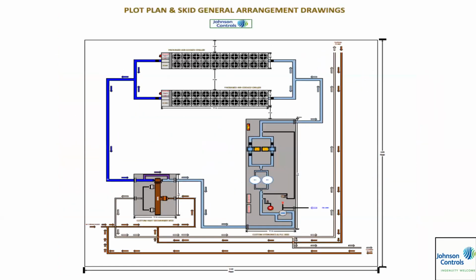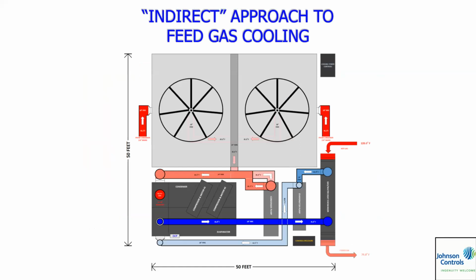This is pentane gas, 2 air cooled chillers with a pentane gas heat exchanger. Skid here, and then here was a pumping skid with buffer tanks and expansion modules. And again, I can show you a bunch of other examples, but this is one with cooling towers. The two cell cooling tower, big double compressor chiller. And in this case, they had no redundancy, which was crazy. So they only wanted 1 condenser pump, 1 evaporator pump, yet they wanted 2 cells and 2 circuits on the chiller, but no redundancy on the pumps. And then there was your feed gas heat exchanger. So that one was with a cooling tower.